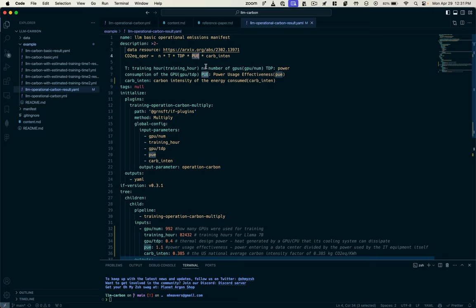which is a data center metric where you calculate the power entering the data center divided by the power used by the equipment within that facility. So essentially the efficiency of the data center times the carbon intensity of the grid. For this, the team used the national average value, but obviously this would depend on the cleanliness of the grid in the region that you were doing your training.